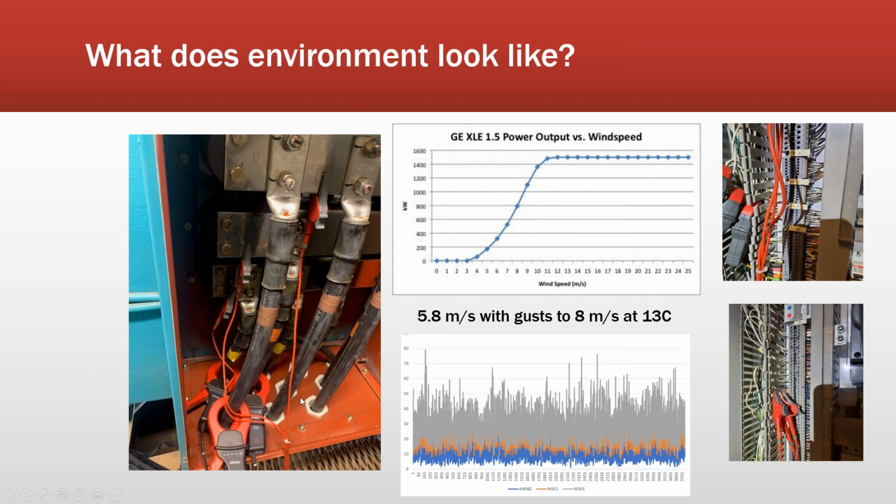When I get this, I will normally not pay too much attention to loose connection readings, because we will detect loose connections. They often happen in the connection box. And then voltage clips here. So we'll put a CT ratio in. For the particular study I'm going to show you, we were right around 5.8, so right around here on the power curve.